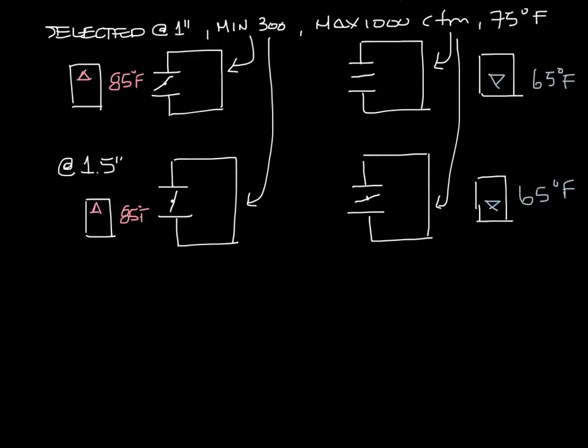And now let's look at the other side of that. Say you only have half an inch inlet pressure. Now you turn up to 85 degrees, but your damper has to open more to provide you the same 300 CFM minimum.